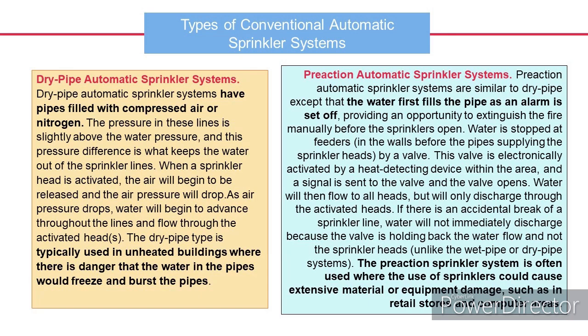Third type is the pre-action automatic sprinkler systems. Pre-action automatic sprinkler systems are similar to dry pipe except that the water first fills the pipe as an alarm is set off, providing an opportunity to extinguish the fire manually before the sprinklers open. Water is stopped at feeders, in the walls before the pipes supplying the sprinkler heads, by a valve. This valve is electronically activated by a heat detecting device within the area, and a signal is sent to the valve and the valve opens.